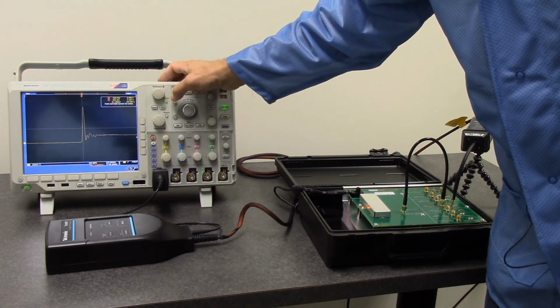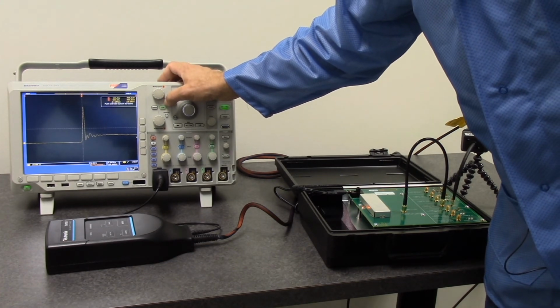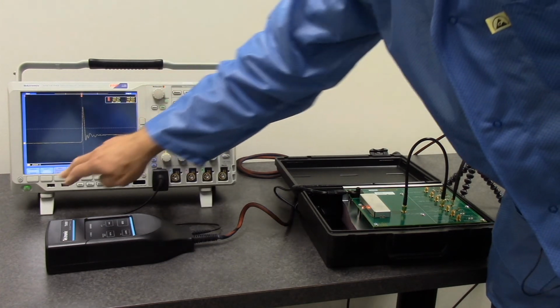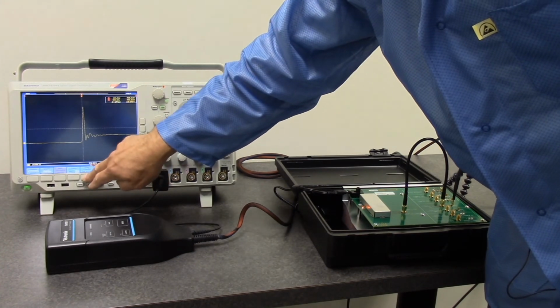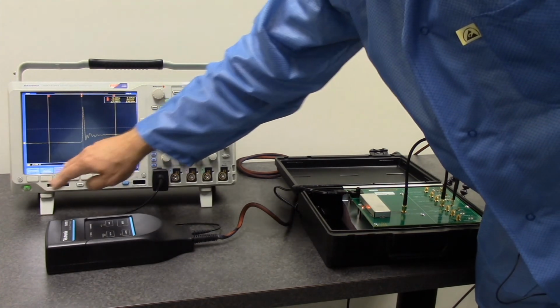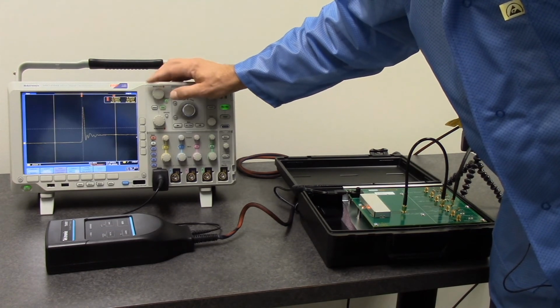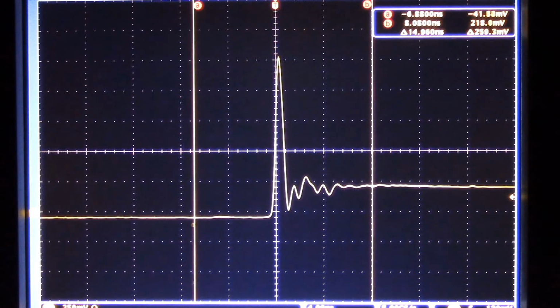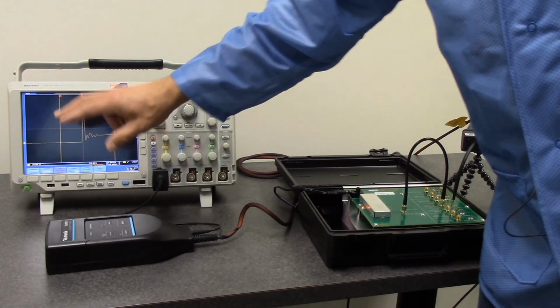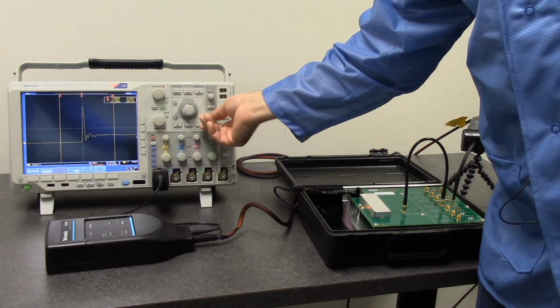The other thing to notice here is this flat level right after the leading edge of the current pulse. We can use the cursors to measure that level. We'll bring the cursors onto the screen, onto the waveform. You can see that this voltage level is being measured with the cursors at about 260 millivolts. 260 millivolts through the 250 milliohm sense resistor gives us a little bit more than 1 amp, so this is a fairly accurate representation of the current pulse that we have through our current sense resistor.